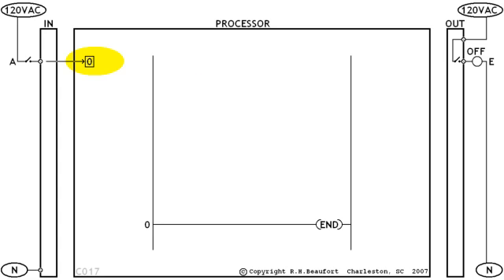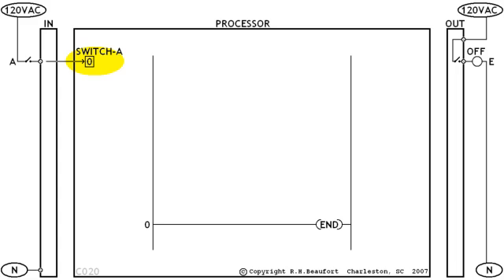Now back to the bit for Switch A. The PLC contains thousands of little bit boxes. We'll need some method to identify exactly which bit we're talking about. That's what the address does for us. Since this is an input bit with an arrow pointing into the box from the field, it'll usually have an address that begins with the letter I, which naturally stands for input. The rest of the address helps nail down exactly which input bit we're dealing with. Different Allen-Bradley platforms use different addressing schemes. So to keep things as simple as possible, we'll assign something like a nickname. It's officially called a symbol, like Switch A. Keep in mind that an actual symbol would use an underscore character instead of a dash, but we've decided to use a dash in our videos because it's easier for you to see on the screen.